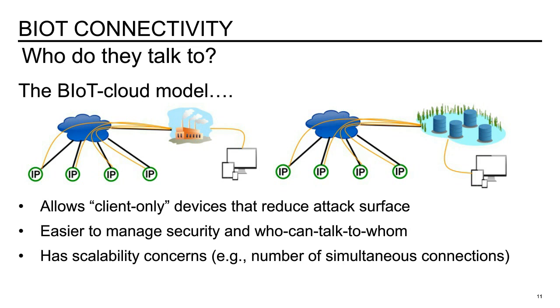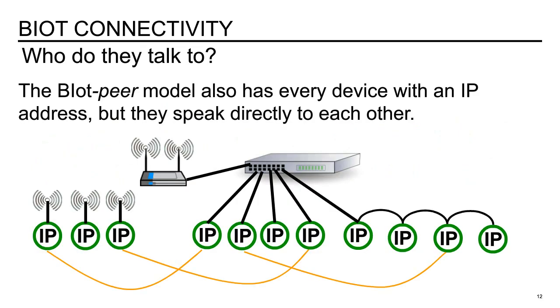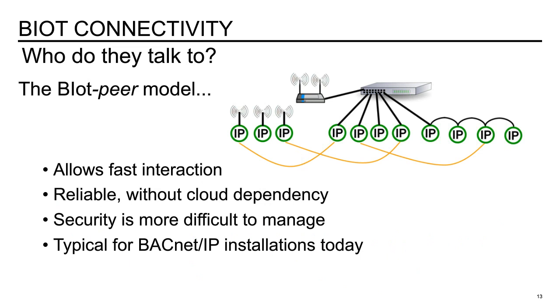So then another aspect is a peer model, where every device has an IP address and they're able to speak directly with each other. So you can see here we've got IP devices across the bottom, and then they're able to talk to each other, not just to a cloud. The advantage of this is it allows fast interaction, it's reliable without cloud dependency, but then security becomes more difficult to manage. And this is a typical installation that we see with building automation systems and BACnet IP devices today. And as I mentioned before, this implementation requires IP addresses for each device, and many times the addresses are required to be static addresses.